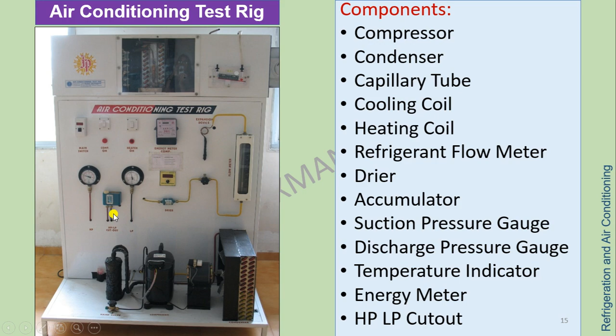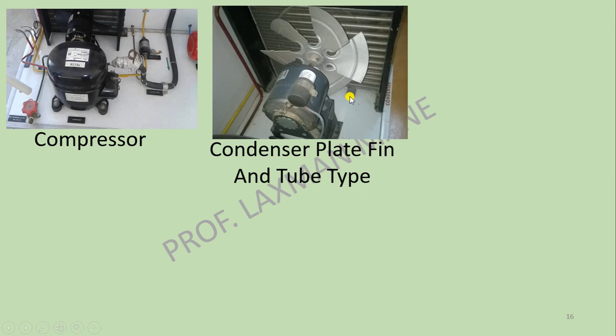This is a hermetically sealed compressor, which is used to compress the vapor refrigerant coming from the evaporator in order to increase its thermal energy level. Thus, its discharge temperature increases above the atmospheric temperature. Such hot vapor refrigerant passes to the condenser, where heat from the refrigerant is rejected to the atmosphere and the refrigerant is condensed. So here is a condenser of plate, fin and tube type. In this, a fan is used in order to have forced convection heat transfer.